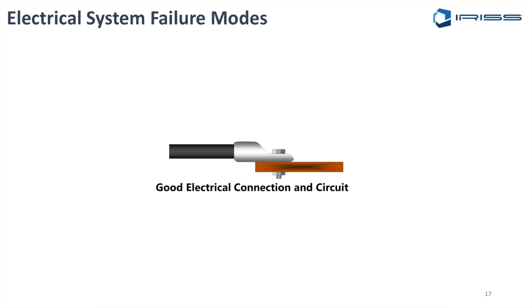In our last presentation, we looked at the electrical failure modes, comparing a good electrical circuit versus a high resistance or loose connection, loose lugs, overloads, partial discharge. We looked at all of these failure modes and the condition-based equipment that can identify them while online, fully energized. Then we looked at what we class as return on safety.